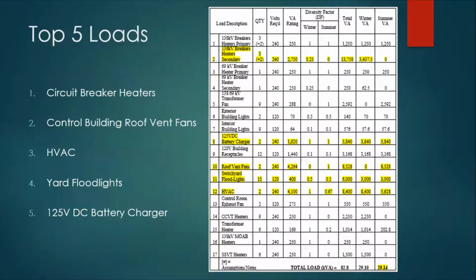The Jackrabbit substation design team compiled a list of major AC consuming loads to properly size the primary and backup SSVTs for all expected loads. Diversity factors, which are a measure of how often the load will be expected to run, were considered for the seasons of winter and summer, since the substation is located in the harsh environment of South Dakota, which can swing over 130 degrees Fahrenheit in a calendar year.